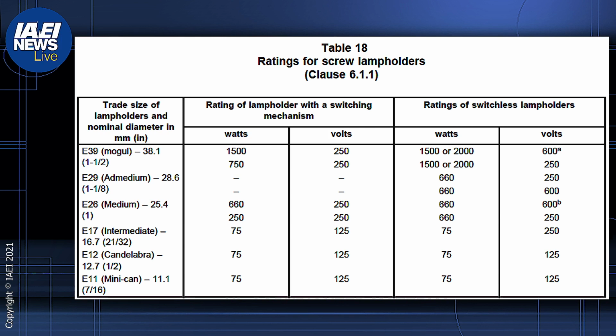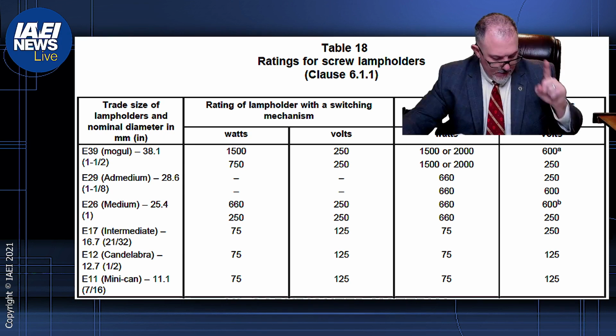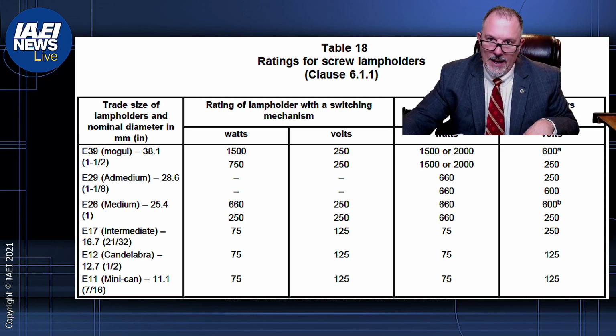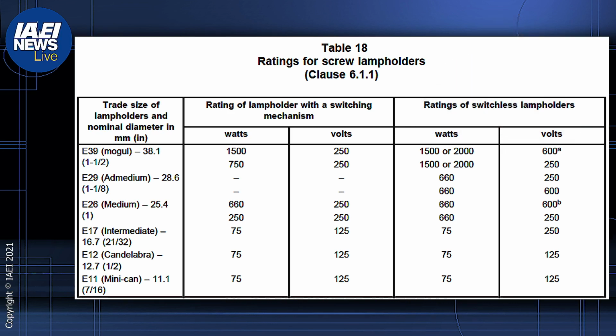This is your rating of the lamp holder. So your mogul base, your E39s, 1500 watts, 250 volts. Rating of the switchless lamp holders, 1500 or 2000, 600 volts. And then your E29 admedium are 660 watts and 250 volts. And if you remember, 210.21(A) told us 660 watts. So that's where that number comes from, 660 watts.